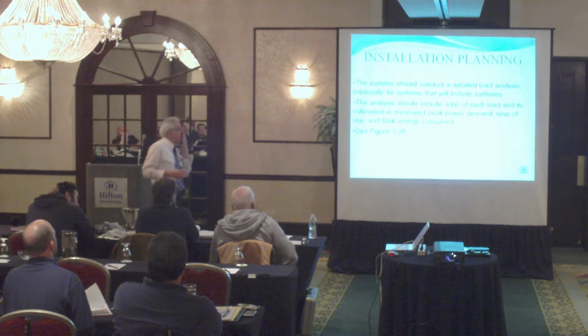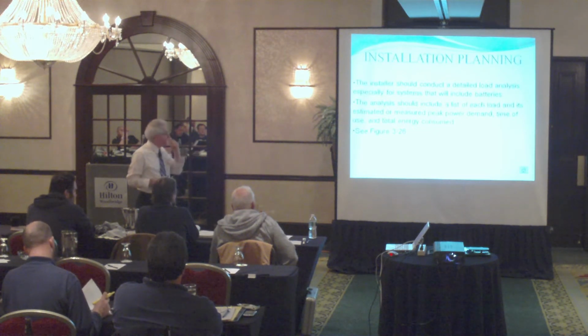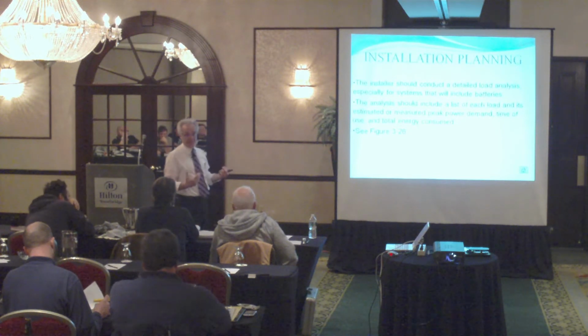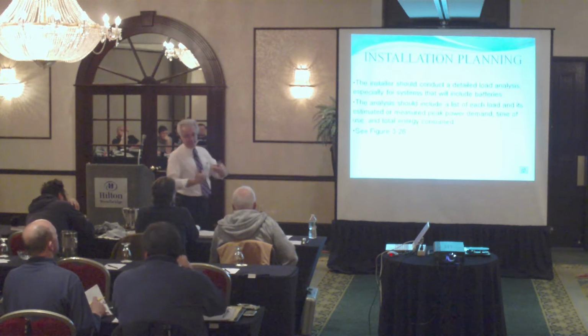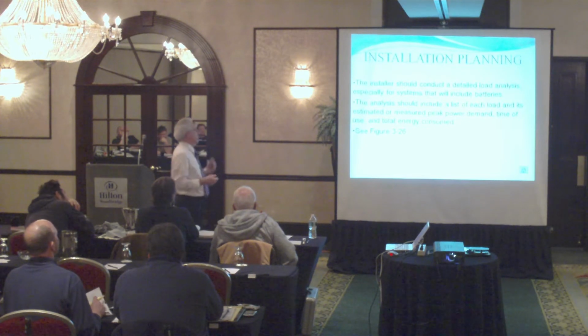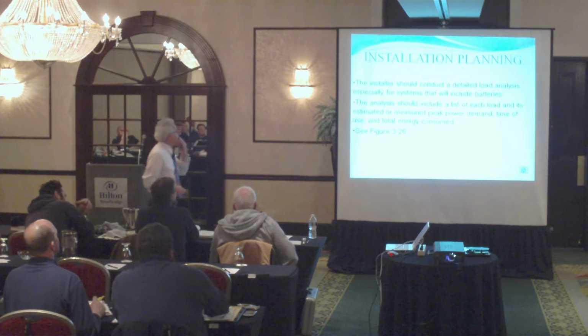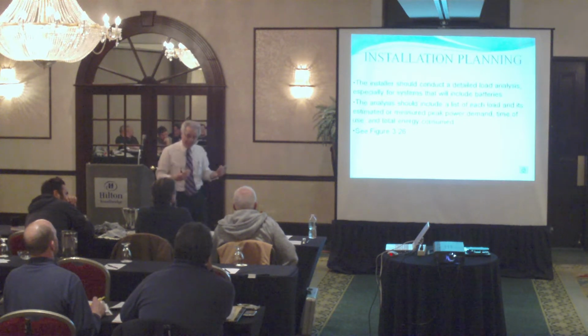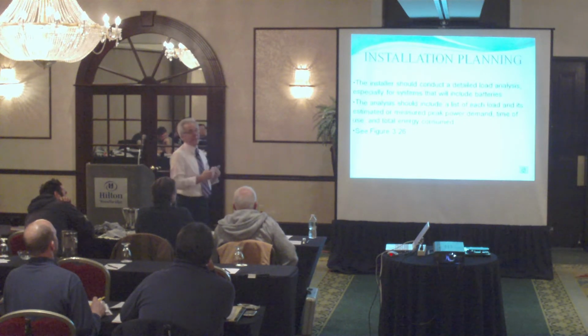Do a very detailed load analysis, okay? If you have to include in any system, what? That is utilize batteries. Because now what do you have to do? You have to charge the battery, so you have to have the right components for that. And if you have to have batteries up there, you have to calculate what kind of loads they need to be, what? To be supported by the batteries in case the system goes down.